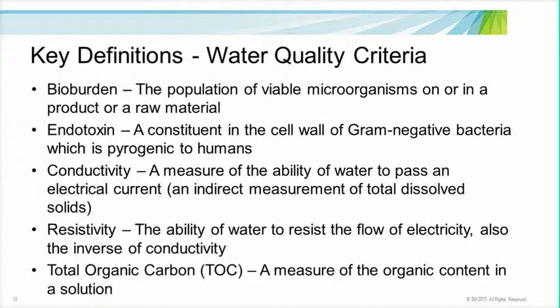Conductivity is the measure of the ability of water to pass through an electrical current. This is also an indirect measurement of total dissolved solids. The inverse of conductivity is resistivity, and this is the ability of water to resist the flow of electricity. Total organic carbon is a measure of the organic content in a solution. This is a very sensitive but not specific test for water quality. So we don't know exactly what carbonaceous material is in water, but we know the exact quantity of it.